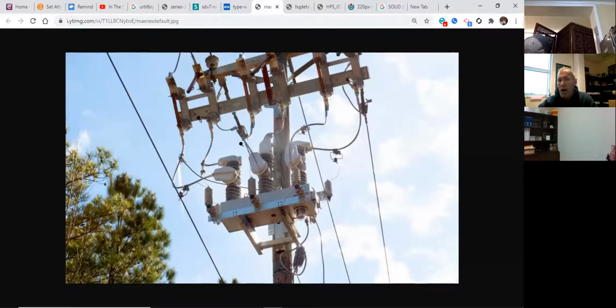No, I want a sectionalizer there to open one time and not reclose. I've got a fault inside a pad mount transformer - is that going to fix itself? No. The sectionalizer is going to open and isolate the whole underground line, leaving the rest of the overhead line hot.